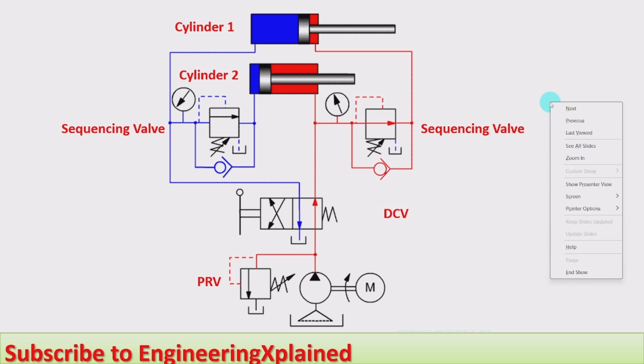The fluid going to the rod end side of cylinder two is blocked by the sequence valve's set pressure — it will not open before complete retraction of cylinder two, and the check valve in that direction is in the closed position. After complete retraction of cylinder two, pressure builds up and the pilot pressure acts on the pressure control valve, opening it. This allows flow through to cylinder one, so retraction of cylinder one begins, with return fluid from cylinder one's piston end side going back to the tank directly, bypassing the sequencing valve.